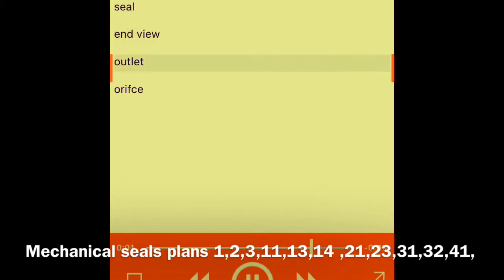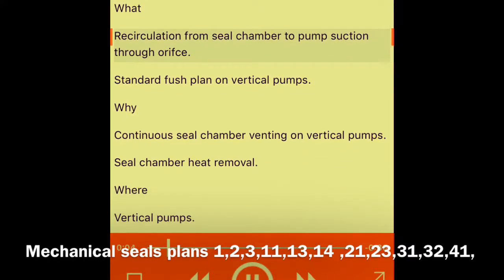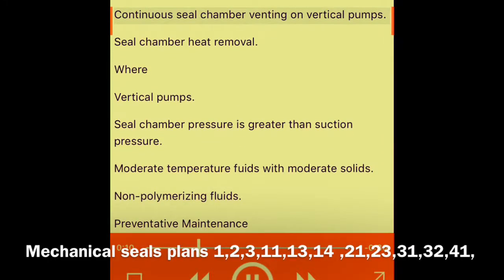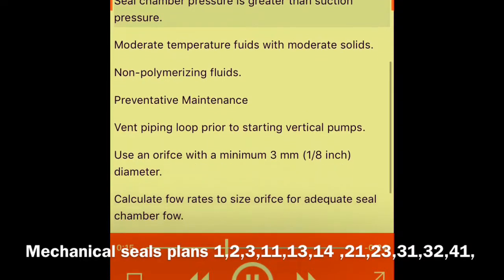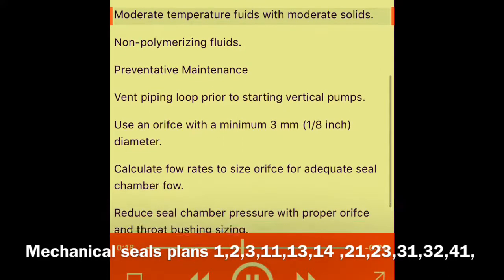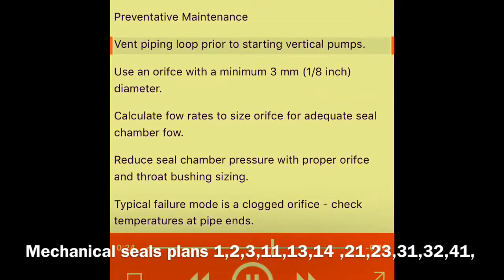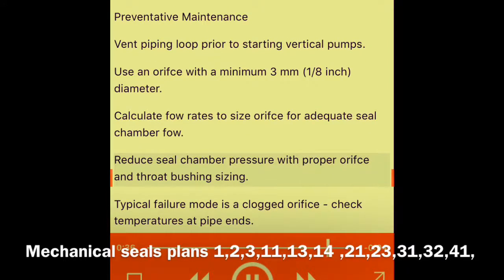Plan 13 — seal end view, outlet orifice. What: recirculation from seal chamber to pump suction through orifice. Standard flush plan on vertical pumps. Why: continuous seal chamber venting on vertical pumps, seal chamber heat removal. Where: vertical pumps where seal chamber pressure is greater than suction pressure; moderate temperature fluids with moderate solids; non-polymerizing fluids. Preventative maintenance: vent piping loop prior to starting vertical pumps; use an orifice with a minimum 3 mm (1/8 inch) diameter; calculate flow rates to size orifice for adequate seal chamber flow; reduce seal chamber pressure with proper orifice and throat bushing sizing. Typical failure mode is a clogged orifice. Check temperatures at pipe ends.